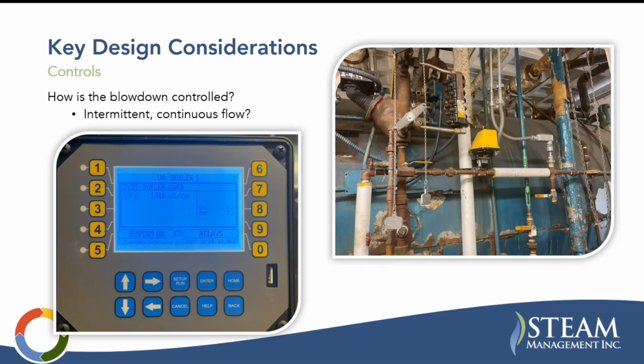Some other things to think about: how is blowdown controlled? Is it intermittent or continuous flow? That might affect your selection of your blowdown heat recovery equipment, as to how it can handle loads or flows that aren't continuous necessarily.